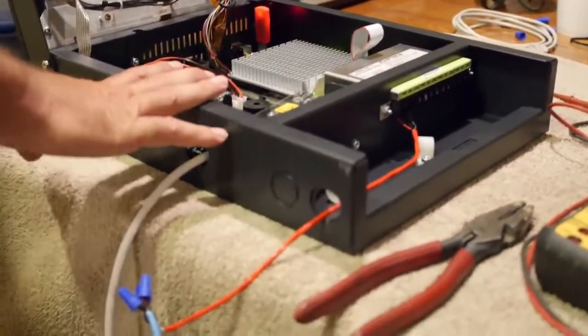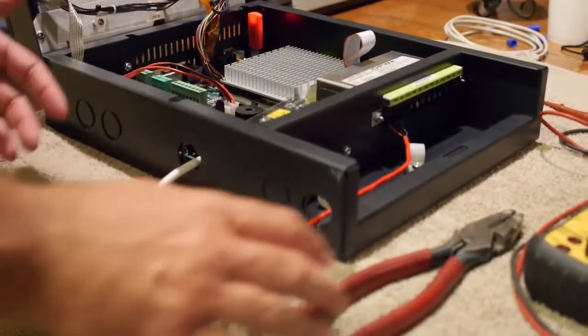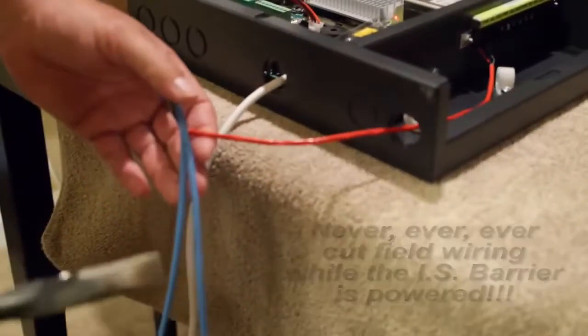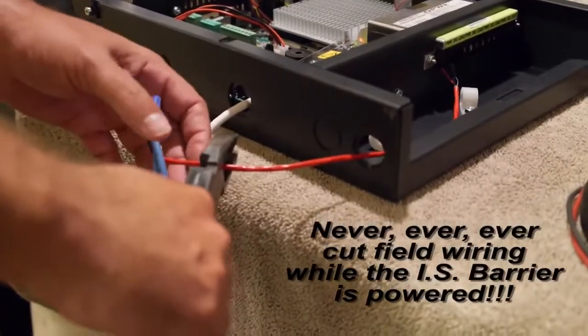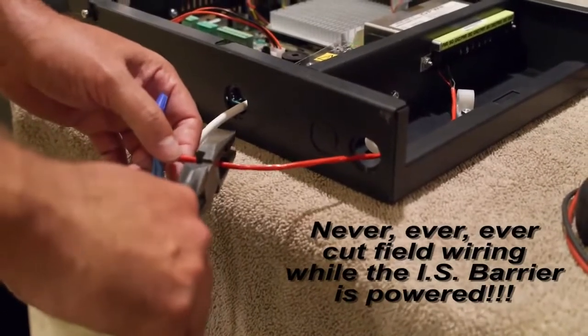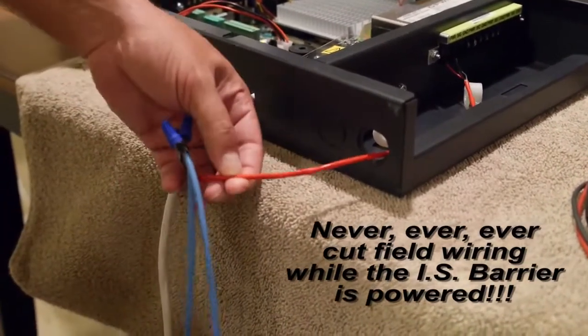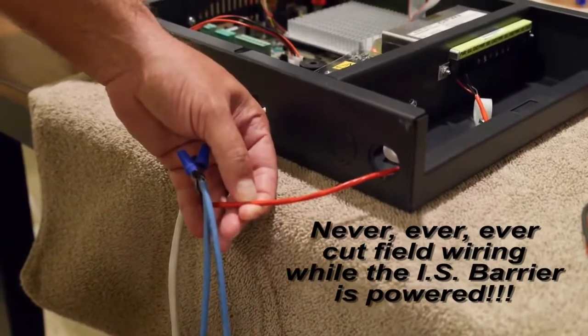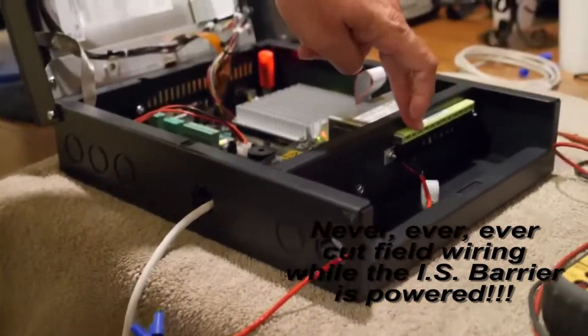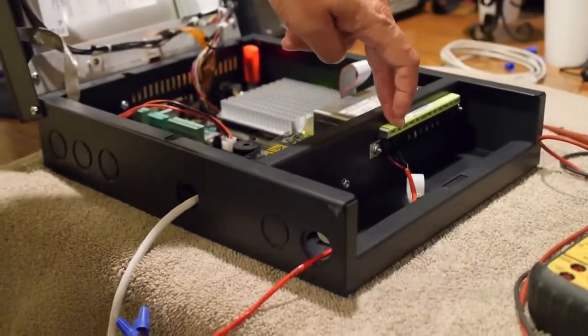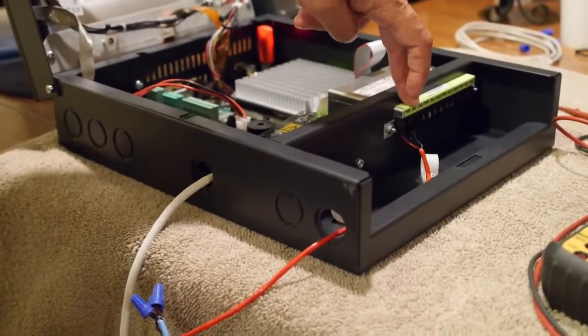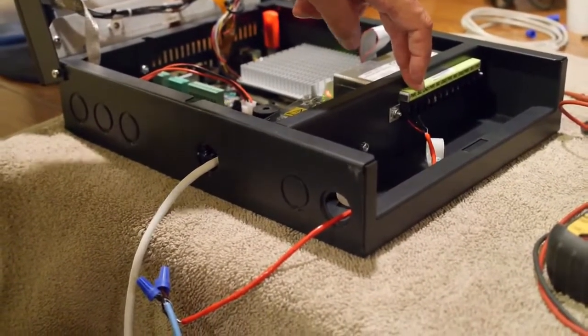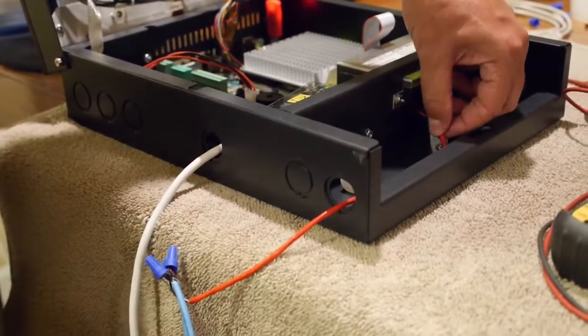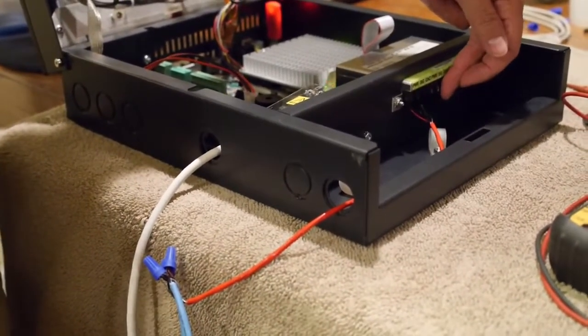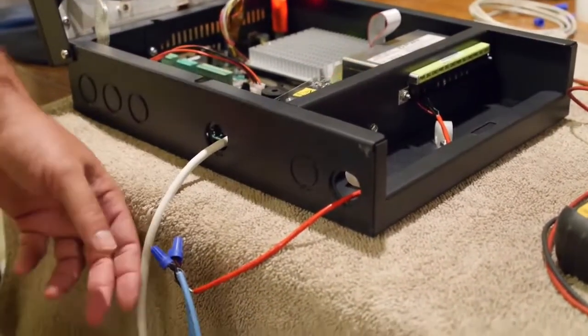Now, this is a hot console. The worst thing that you can do in the field is go out and grab your linemen and cut directly across the wires themselves, because you're going to short the power and the ground together, and you're going to actually blow the barrier. If you're reading 0 volts on the barrier, then you've blown that barrier. What you could do is move this wire to an open barrier position, rewire, and do an auto detect.